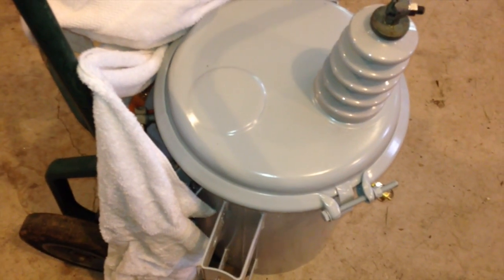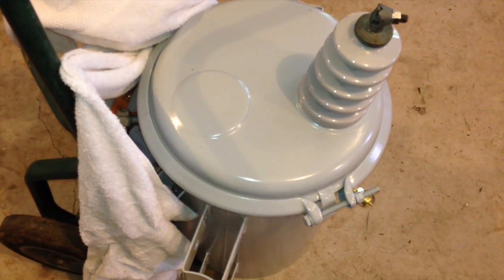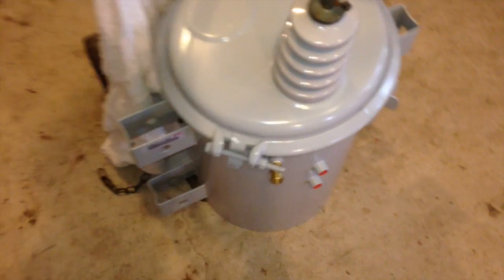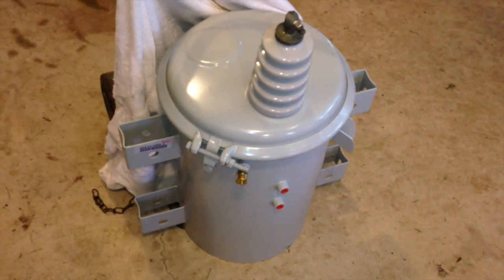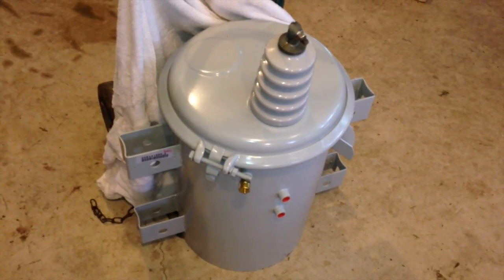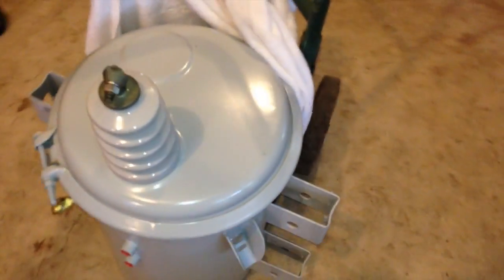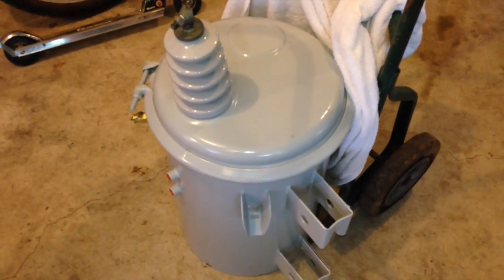I do believe this one is 280 pounds. The 15 kVA one, that weight's probably wrong—probably just the core and the tank without the oil, because this only has 5 gallons of oil in it.